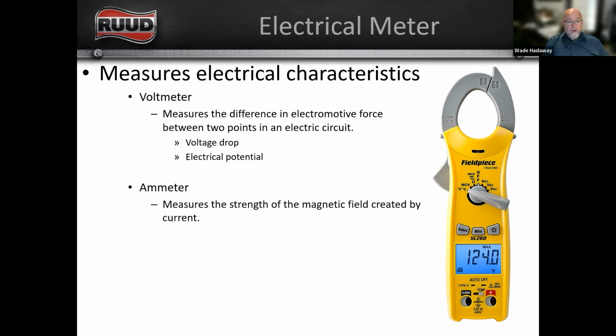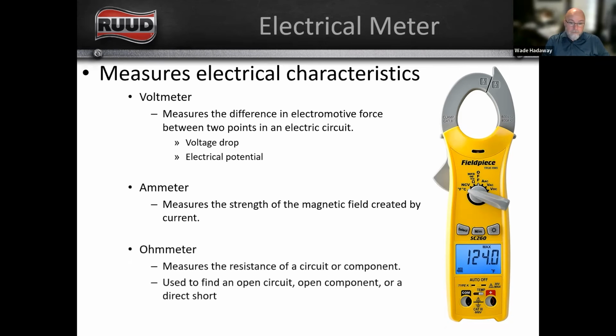Typically, your multimeter has an ammeter so that you can measure amperage or current, and that is the clamp up at the top of this meter that's depicted. It measures the strength of the magnetic field that's created by the electrons moving through the wire or through the conductor. And then typically it's got an ohmmeter, and to check ohms, the symbol is an omega. The ohmmeter we use to measure ohms, or to find the resistance. We can use that to determine if we have an open circuit, if we have a component that has failed or is open, or if we have a direct short. And I'll go through a couple of examples of that here in just a minute.